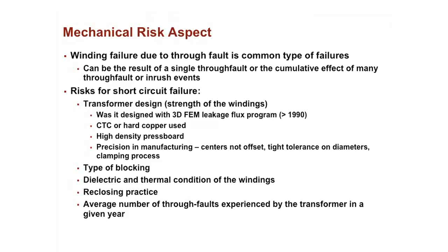You also look at the dielectric and thermal condition of the windings. Windings that have aged a lot, meaning the cellulose has aged and reached the end of its life, are going to be much more susceptible to a short circuit failure than ones with paper that's not very aged. And then also the reclosing practice. So when there is a fault, is there automatic reclosing, or what is the reclosing practice? And then also the average number of through faults per year experienced by a transformer. Depending on where a transformer is in the grid, it can see fewer or more through faults, and also differing sizes of through faults. Some transformers by nature see a lot of through faults, like industrial transformers, but they're usually designed a little bit differently to sustain short circuit forces much more. But all these things go into account when you're calculating the risk of short circuit failure.